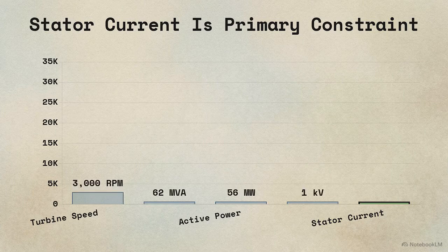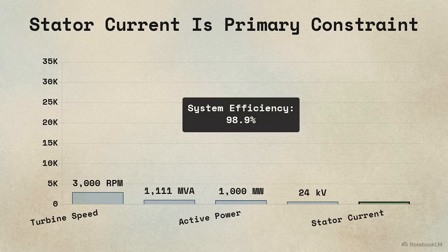Looking at this digital dashboard, the raw output metrics define the scale of the operation. Driven by a steam turbine at a constant 3,000 revolutions per minute, it yields 1,111 megavolt amperes to produce a full 1,000 megawatts of active power at 24 kilovolts. And it achieves all of this at 98.9% efficiency.